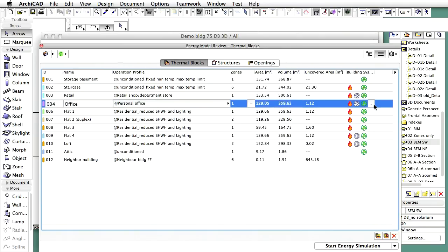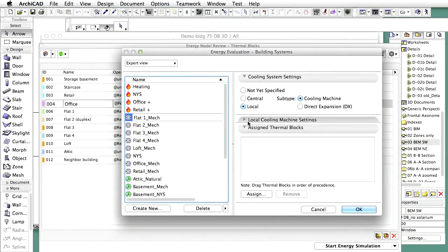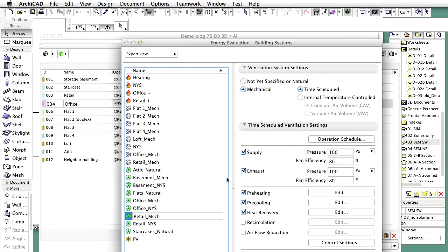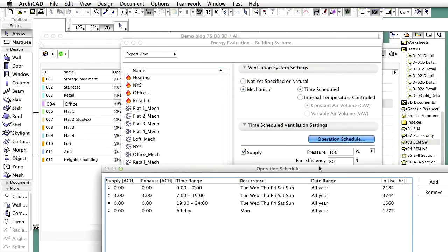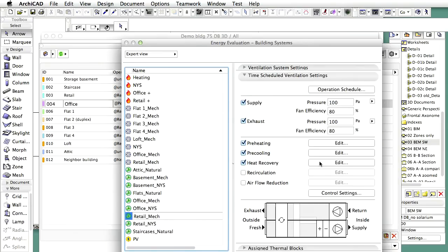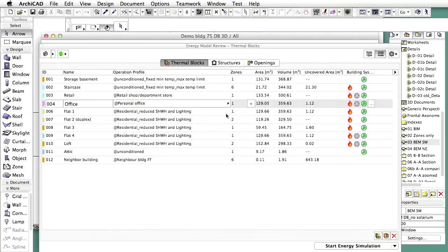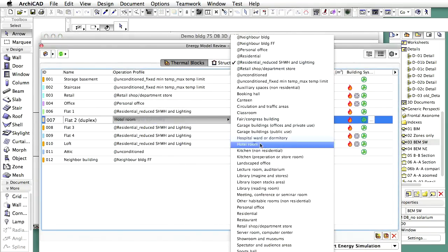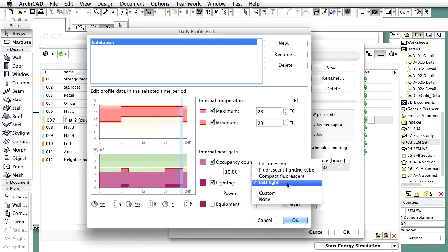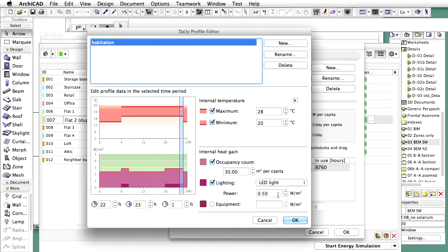For thermal blocks that do require mechanical cooling, for example the office, cooling systems with less capacity than the baseline project are suitable. The mechanical ventilation systems, for example in the retail thermal zones, are time-scheduled and equipped with modern air-to-air heat recovery modules, meaning the heat of the exhaust air is used to preheat the fresh air. Modern energy-efficient LED lighting fixtures are used in the residential thermal blocks instead of incandescent lamps, since LEDs produce much less heat while providing the required level of artificial illumination.